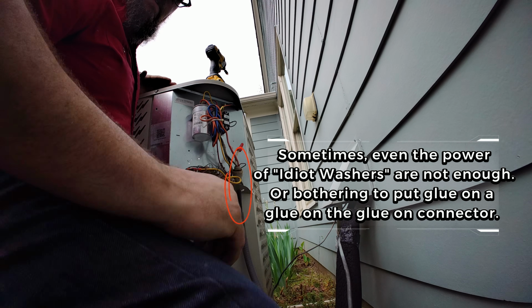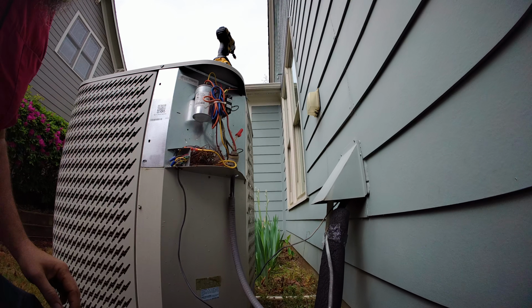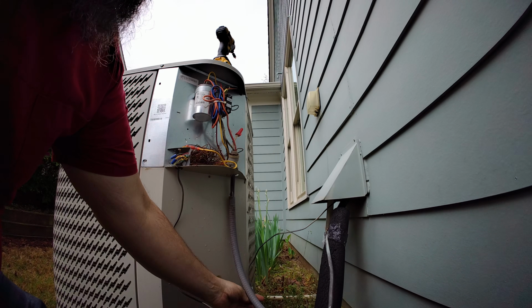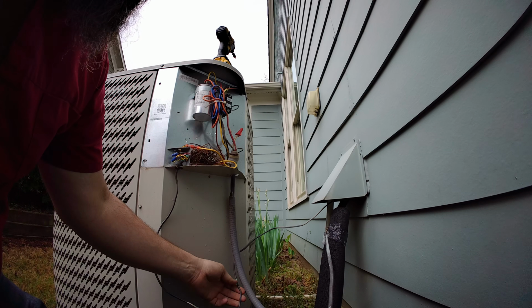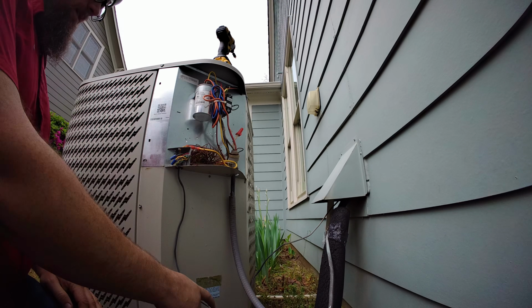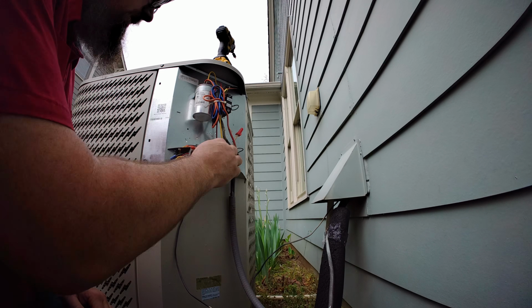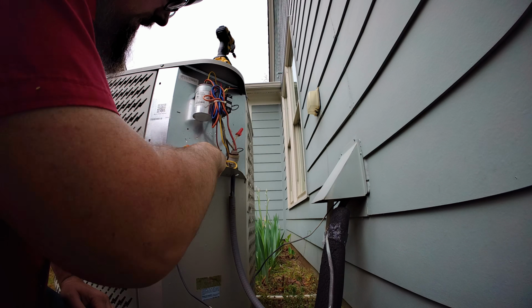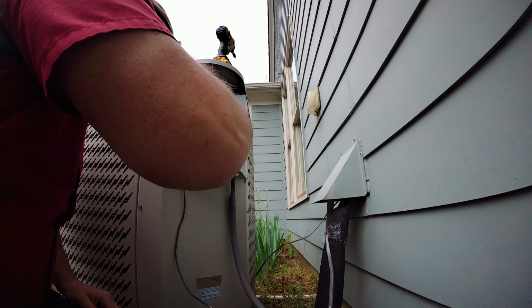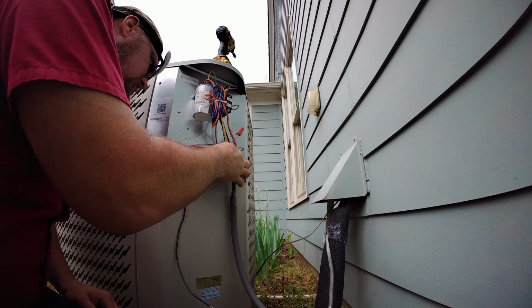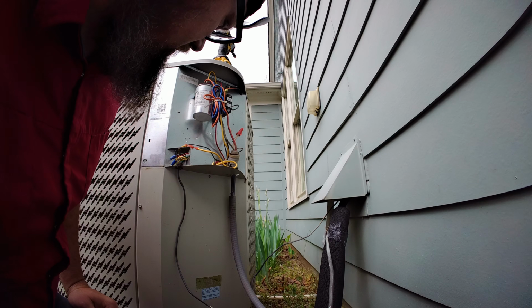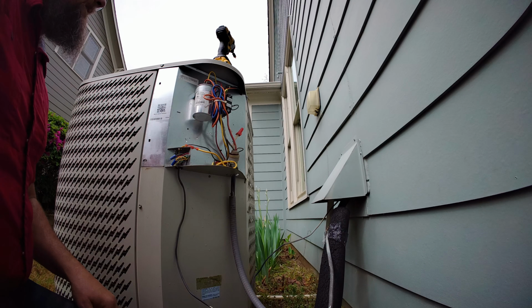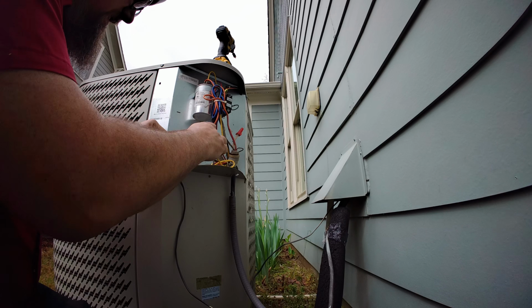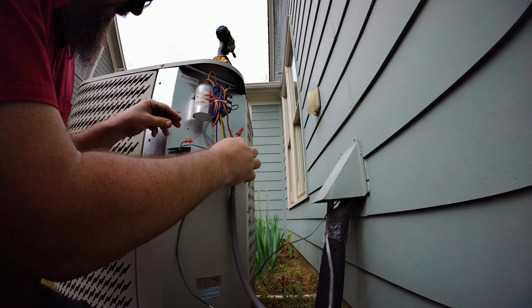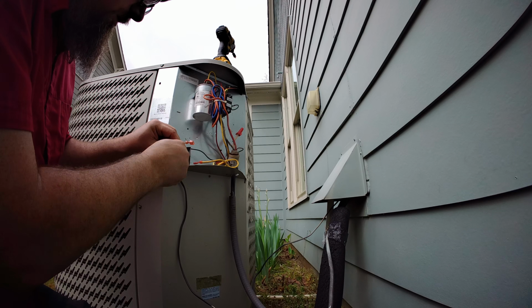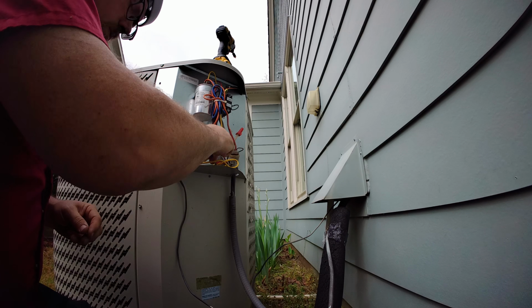Alright, first thing we notice is we do have some damaged wire, but that's probably a weed eater. Doesn't seem to be actually interfering with the internal insulation on these wires. I do see a little bit of a mess there. I don't see actually any wire damage where a rodent or something was in here. Let us just disconnect here. See if we have any kind of shorts going on the outdoor unit.